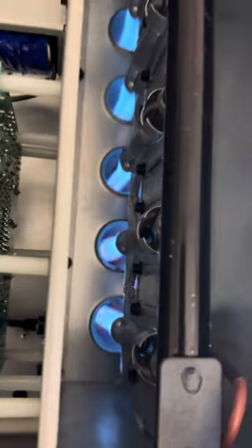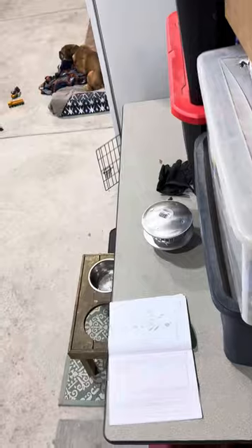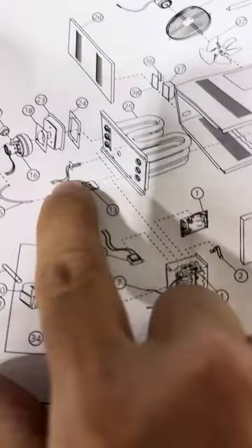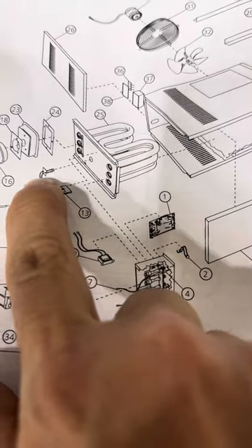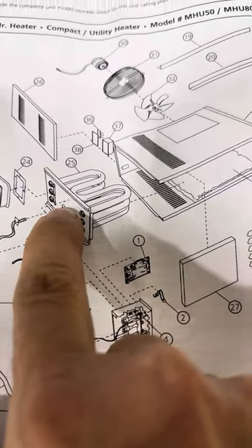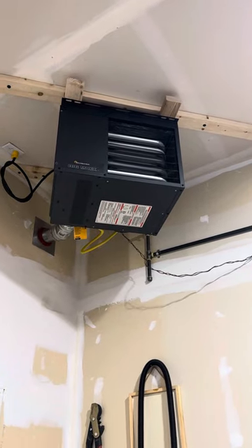Now my heat sensor for the heat exchanger — let me get down here, watch out Heidi — this is what they call the high limit sensor in the heat exchanger. When that heat exchanger gets too hot, it's going to shut off that blue flame.